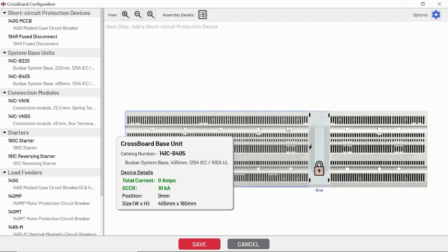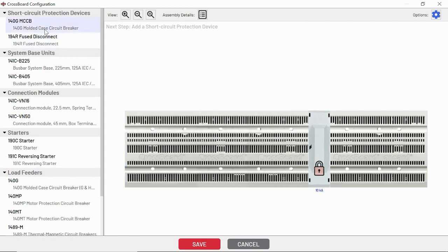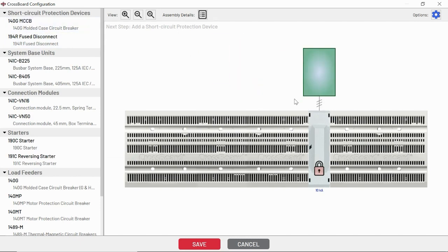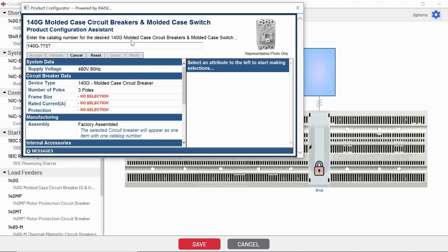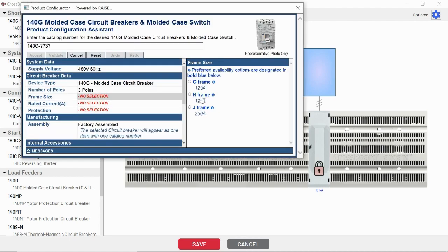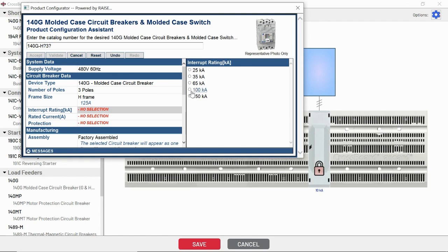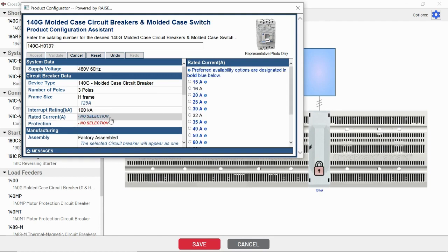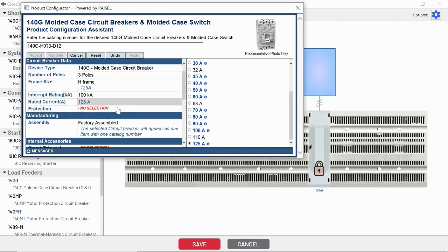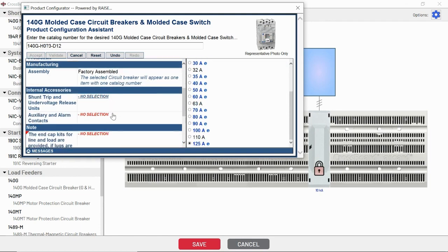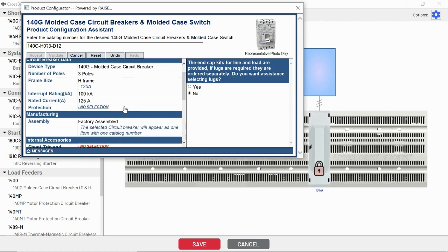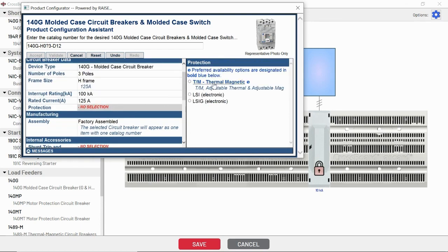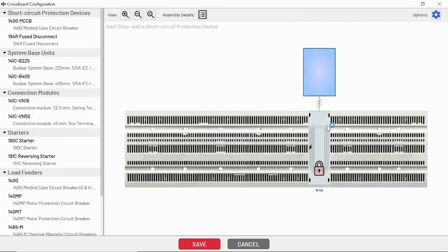Next, we're going to decide how we want to feed this crossboard. If we're going to feed from a panel mount short circuit protection device, we can pick from these two in this software right now. I'm going to go ahead and configure a 140G. This is going to pop up in a ProposalWorks configuration window, very similar to what we're used to seeing already. Something you'll notice with this tool is it's going to keep track of our SCCR rating for us as we go. That's pretty handy.